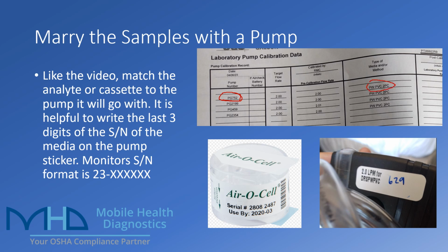So we're going to take that and match that to the actual material collection on it. You'll look at the cassette, match up that it's the same type, and then, to make things easier for the setup day, you take the last 3 serial numbers on the serial number and write it down on the pump sticker right there. So then when you have the testing day, you can take the cassette, easily find the pump that was calibrated specifically for it, and just attach them, and you're pretty much ready to go. So you'll want to do that for each one of the different pumps.